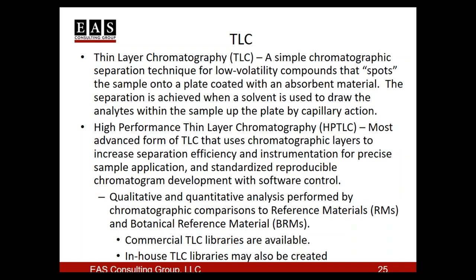The key is to make sure that reference material, or botanical reference material, has been appropriately characterized. It's also very important using HPTLC that if you're using a botanical plant, whether a powder or an extract, the reference material must match. A powdered material cannot be used as reference material for an extract, because they haven't gone through the same process.